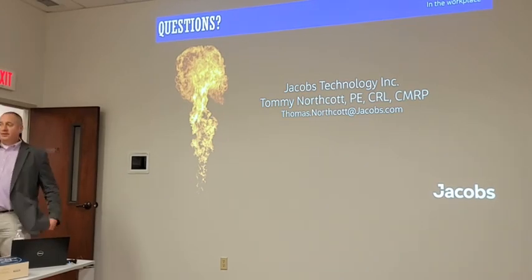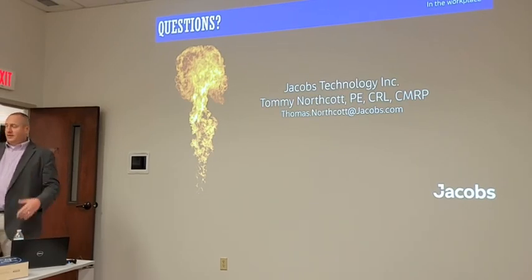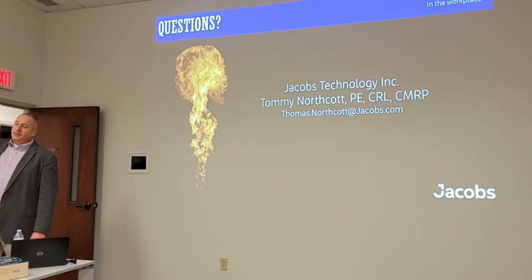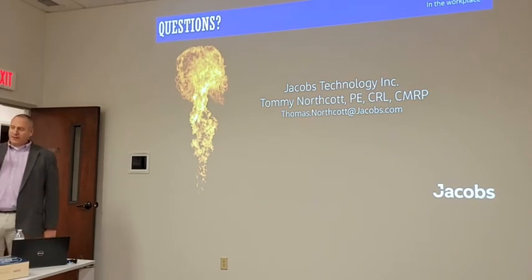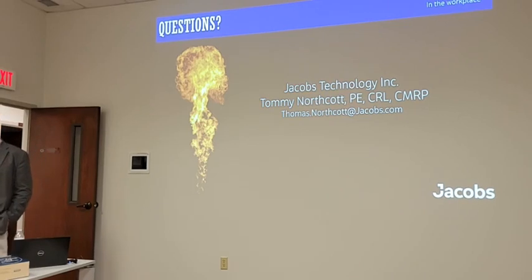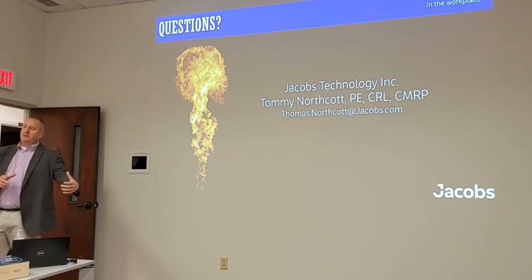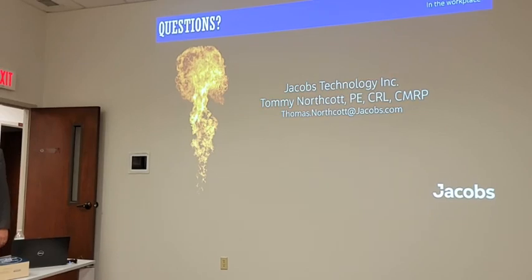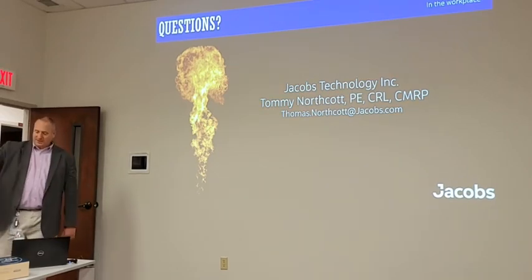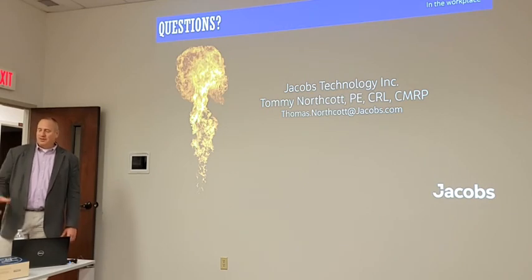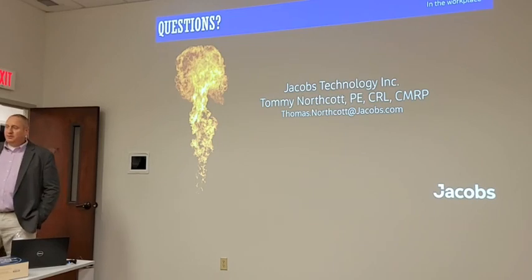I see. Now, if it's a remote HMI operating station and the contactor is on the other side of the room and you're outside the boundary, then you can. Right. But if it's inside that enclosure and 480 volt contacts are making and breaking contact inside that enclosure, then you've got to wear the arc flash PPE. And we've actually had scenarios where the specification called for remote operations and a racking box, and the contractor designed it to be sitting on the side of the gear. So for the 3 or 4 on the opposite end, you're outside the boundary of those, that's great, but for all the ones here, it really bought you nothing. So you need to make sure all those remote controls are outside the boundary of the equipment that's actually operating.